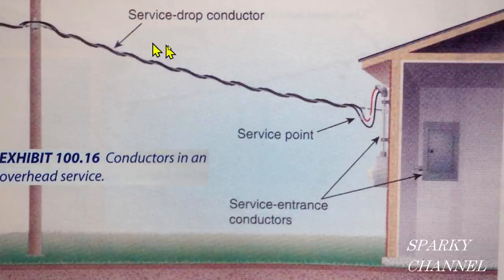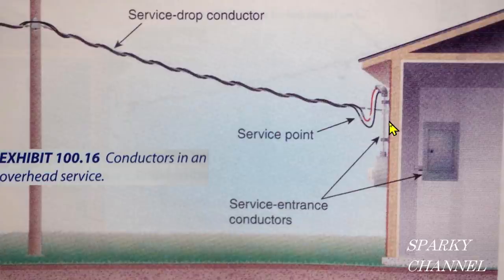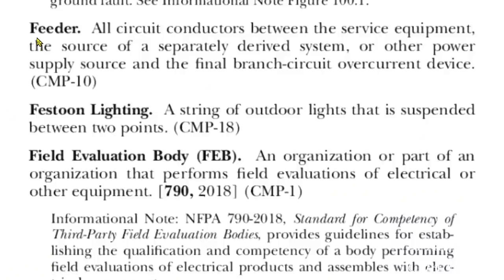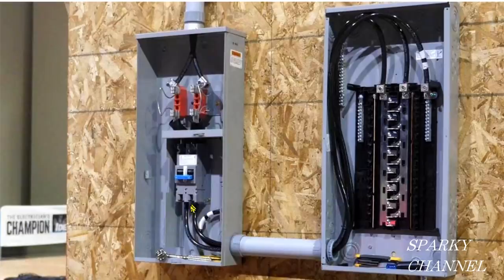Here's the pole, here's the service drop conductor, and here's the service point — this is where the utility has hooked up to your wires. These are service entrance conductors. Here's your meter — there's no service disconnect in this meter, therefore these are service entrance conductors as well. And here in Article 100, here's the definition of feeder: "All circuit conductors between the service equipment, the source of a separately derived system, or other power supply source, and the final branch circuit overcurrent device." So these conductors right here are feeder conductors, and then you would have your circuit breakers with branch circuit conductors coming off of them.